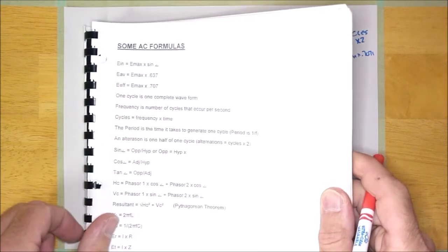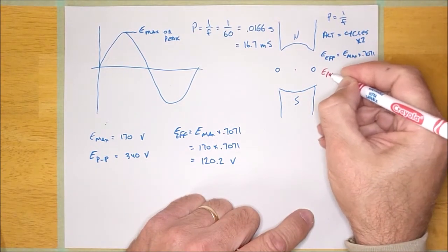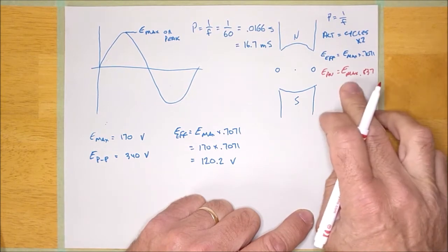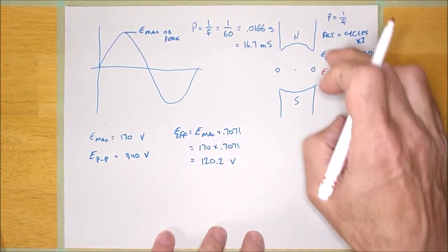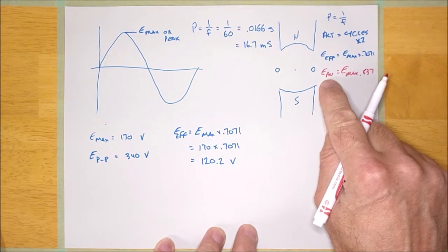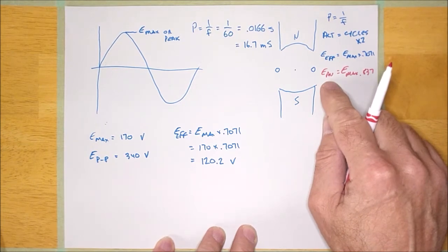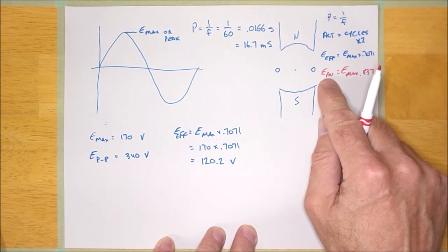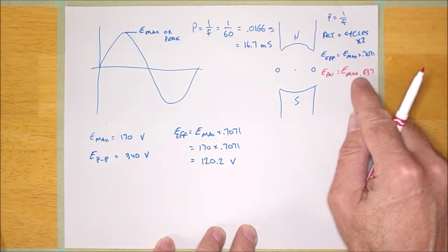So if we look at it here, it says E average is equal to E max times 0.637. I'm going to write it down right over here. E average is going to be E max times 0.637. Now, what are they talking about? Average voltage — it's different than the effective voltage. The multiplier is different. The average voltage is calculated when you've done some rectification, because the average voltage is also the DC voltage. Average is always DC.